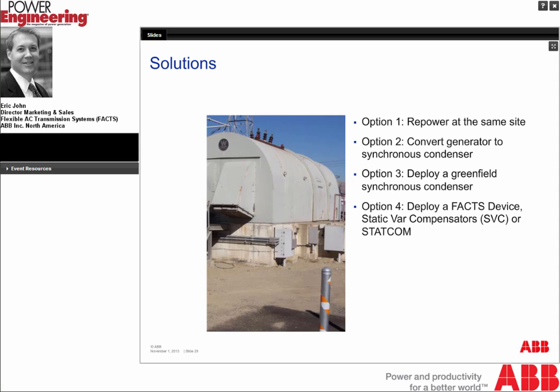The focus of the solutions covered here today are those solutions that are dynamic in nature, meaning that they can change their output rapidly and that they have the capability to control their output on a continuous or a vernier basis. The rationale for focusing on a dynamic solution is that a power plant, by its nature, is a dynamic source of reactive power. So if a power plant goes away and reactive power is very location dependent, and you have loads physically close to where this retired power plant was located that need dynamic reactive support, it stands to reason that the types of solutions that should be studied are also dynamic in nature.